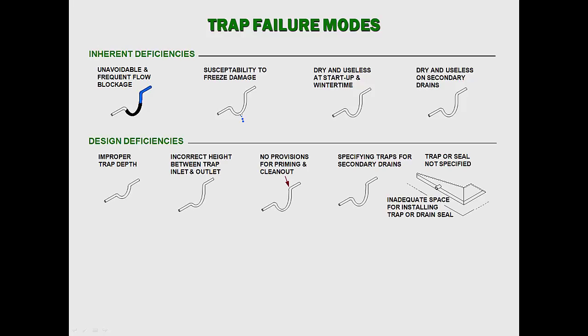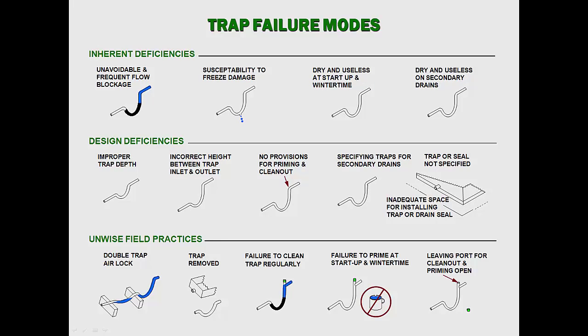Design deficiencies of traps include improper trap depth, incorrect height between trap inlet and outlet, no provisions for priming and clean-out, specifying traps for secondary drains, trap or drain seal not specified, or inadequate space for installing a trap or drain seal. Unwise field practices include double-trap airlock, trap removed, failure to clean trap regularly, failure to prime at start-up and wintertime, and leaving the port for clean-out and priming open.